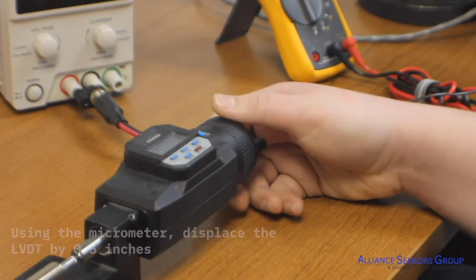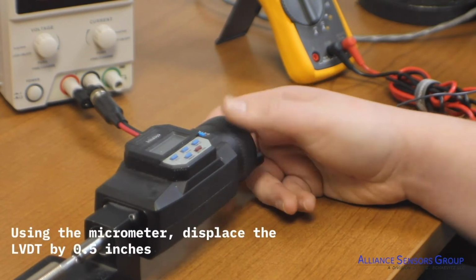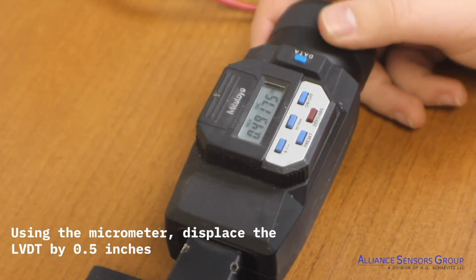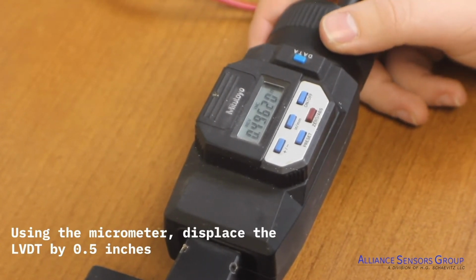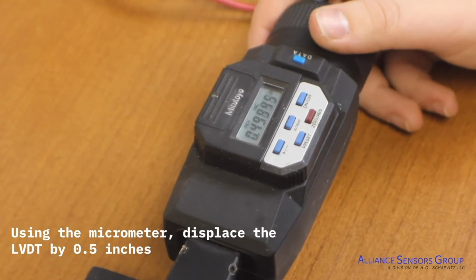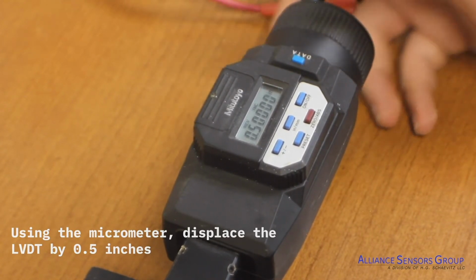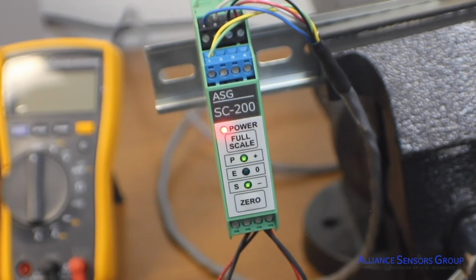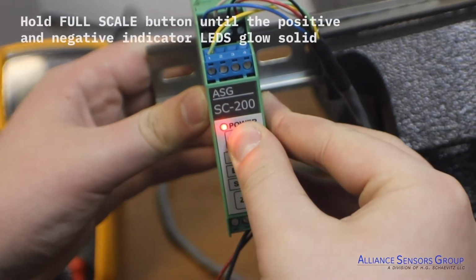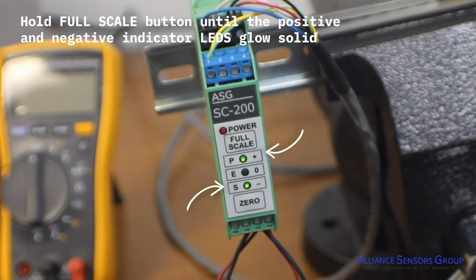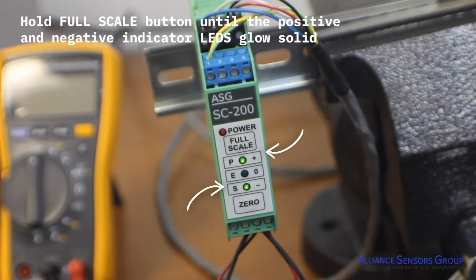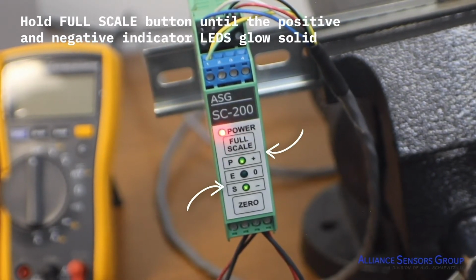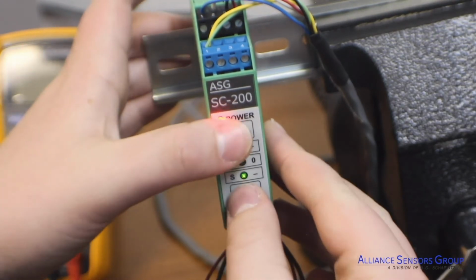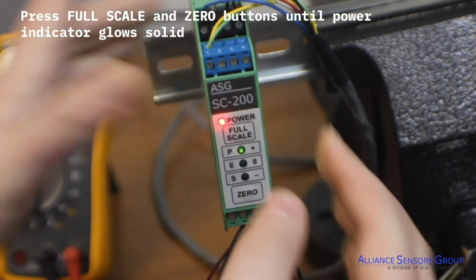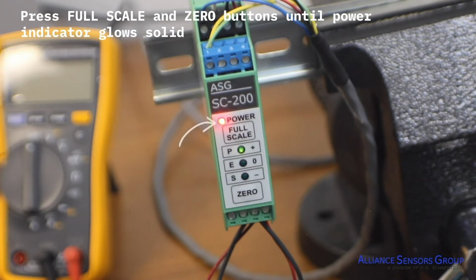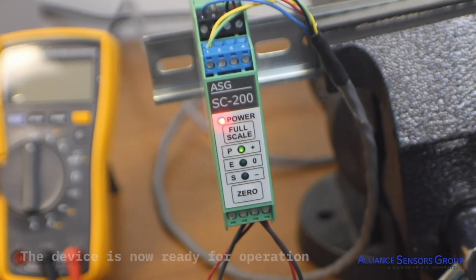Next, we displace the LVDT by plus 0.5 inches. This will take us to the positive end, or 0.5 inch position of the LVDT's stroke range, and will be the SC-200's 10 VDC output position. When the position has been reached, momentarily hold the full scale button until both the positive and the negative indicators illuminate solid. This indicates that the calibration has been successfully completed. Finally, to return the SC-200 to operation mode, press both the full scale and 0 buttons until the power indicator glows solid. The device is now ready for operation.